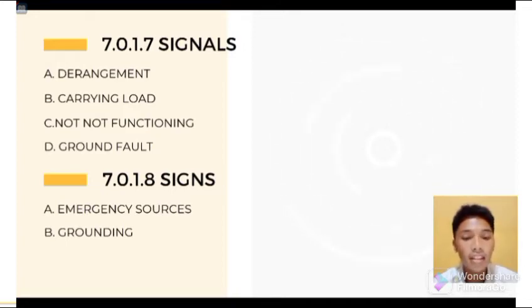to the ground and circuit protective devices rated to 1000 amperes or more. The sensor for the ground fault signal devices shall be located at or ahead of the main system disconnecting means for the emergency source, and the maximum setting of the signal devices shall be for a ground fault current of 1200 amperes. Instructions on the course of action to be taken in the event of indicated ground fault shall be located at or near the sensor location. So, it is important to take note of that.